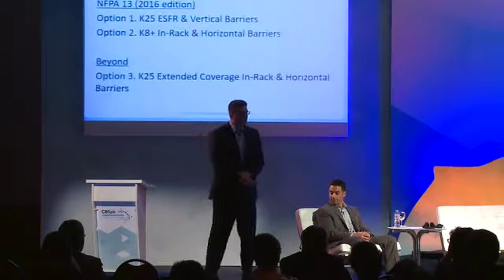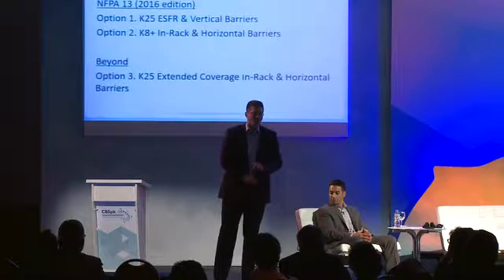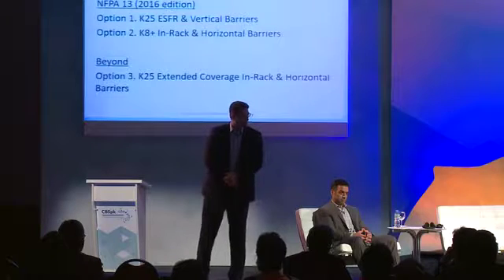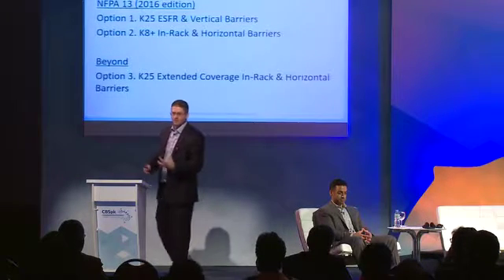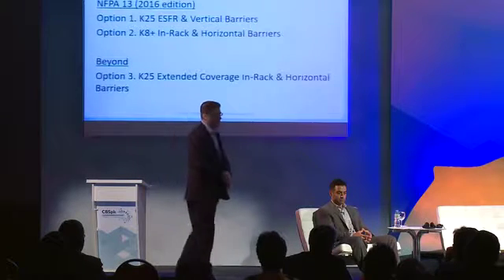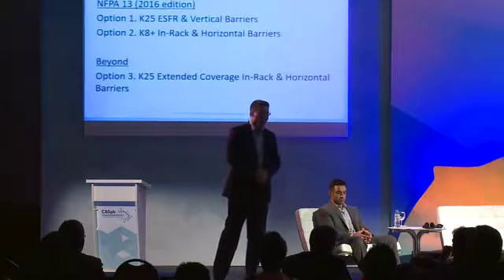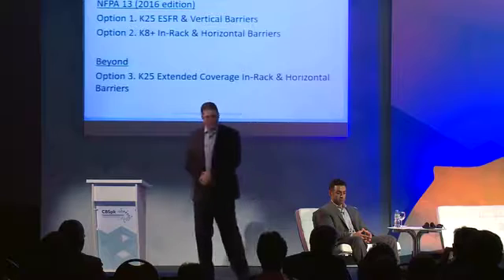Then we get to the 2016 edition. All of a sudden, we have two new criteria for something that could never be protected before with an NFPA 13 criteria. We have one involving K25 ESFR sprinklers and vertical barriers. Carrie Bell is going to talk a lot about the research and the work that went into developing that criteria. There's also a protection scheme using K8 or larger in-rack sprinklers with horizontal barriers. And that we'll talk about a little bit here.